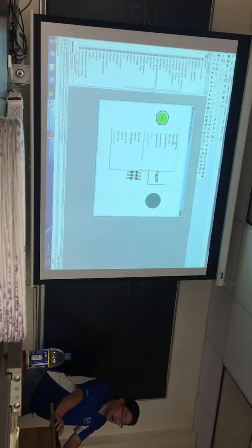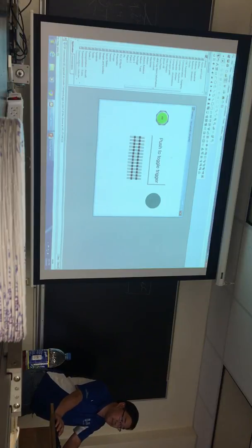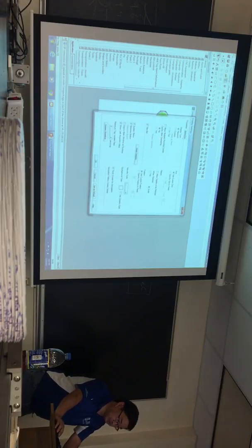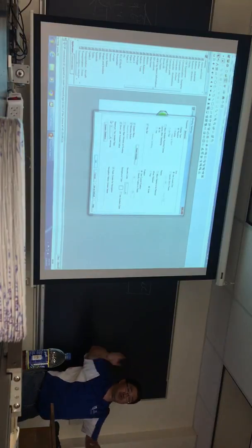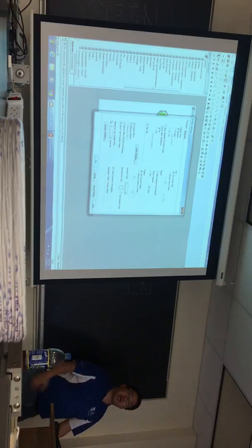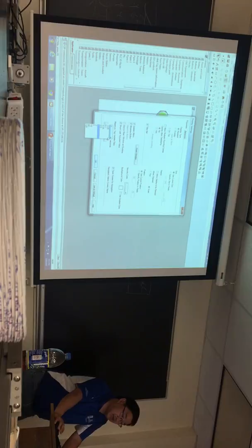Something else you need to be aware of. The first time you start a screen, if you right click and go to display options, settings, excuse me, maximum tag update rate, 1 second. By default, they only update the screen every second. So no matter what the tags are doing in the background, the screen will not reflect any changes for 1 second. I think it's to keep control of network traffic, because this has the potential of wanting to suck a lot of data through that network.